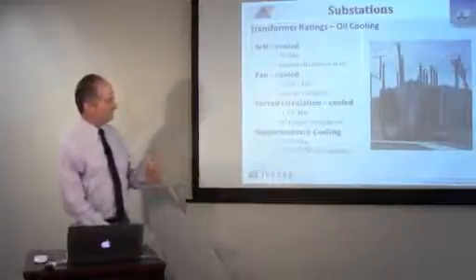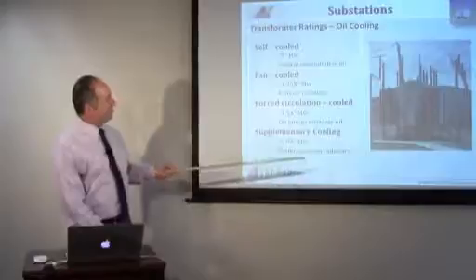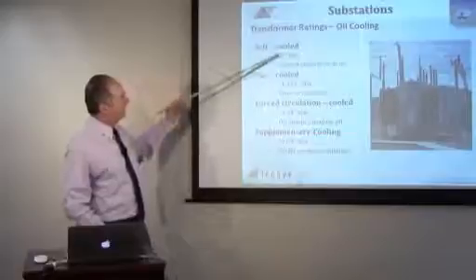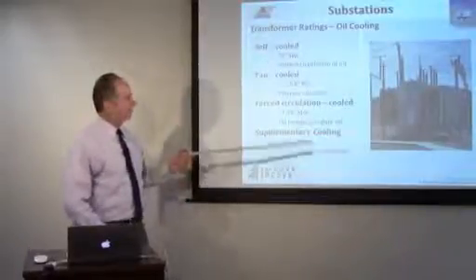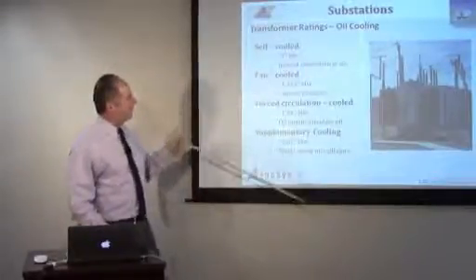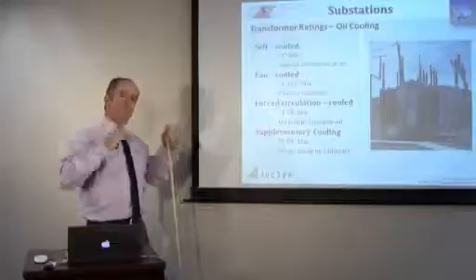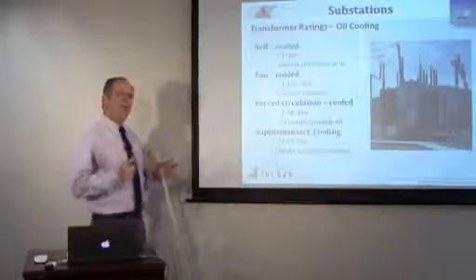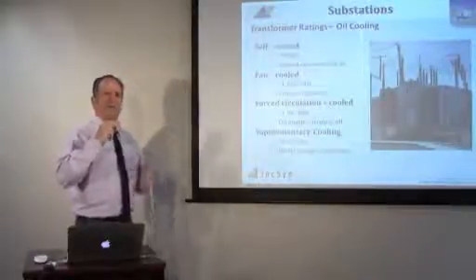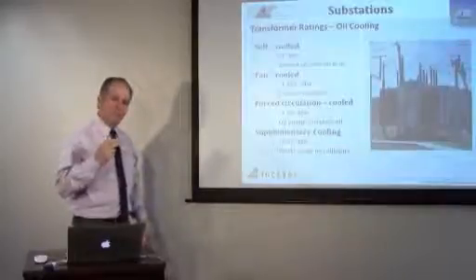Now, transformers have different oil ratings or different power ratings. When you don't have the fans turned on and you're just using convection cooling, that would be considered the self-cooling of a transformer. And let's say this one happens to be a 150 MVA self-cooled. When you turn on the fans, you might get an extra 25% more power through before the temperature rises above its rating. Normally, a transformer's temperature rises to 60 degrees at full load. You don't want to go higher than that. So if it starts getting higher, turn on the fans to keep it at 60. But now you get to load it up more, keeping it still at 60.